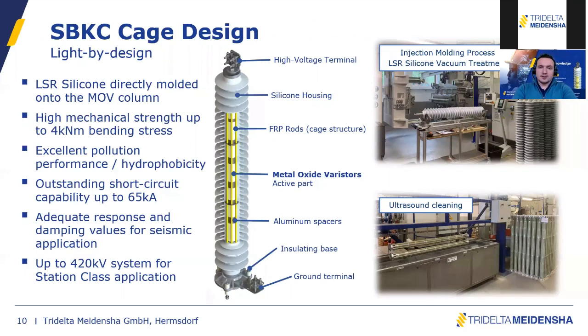So I will go quickly through the different designs. I think it's important, before going into a typical arrester configuration, to look at the voltage ratings, the energy ratings, the mechanical strength, and the short circuit performance and all those things. It's important to understand the different designs which are available from the different manufacturers. One that you can find from different manufacturers is called a cage design. It's a polymer surge arrester where the silicone is directly molded onto the active part.